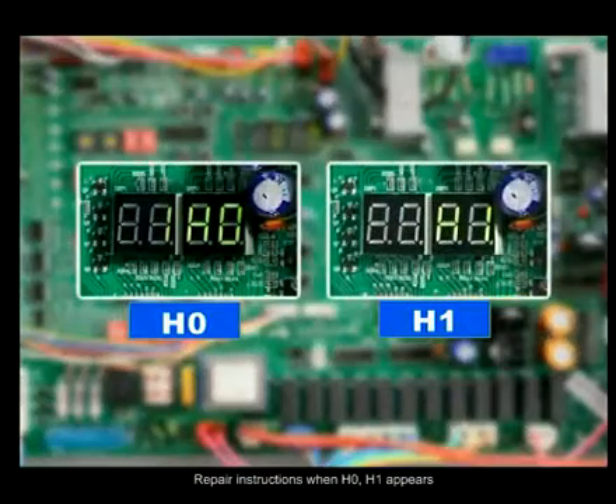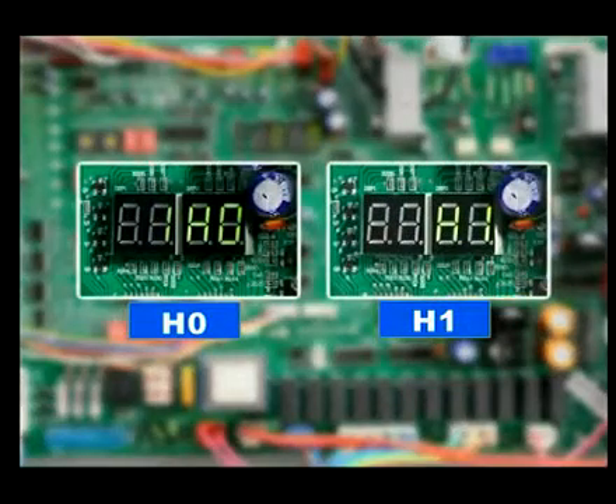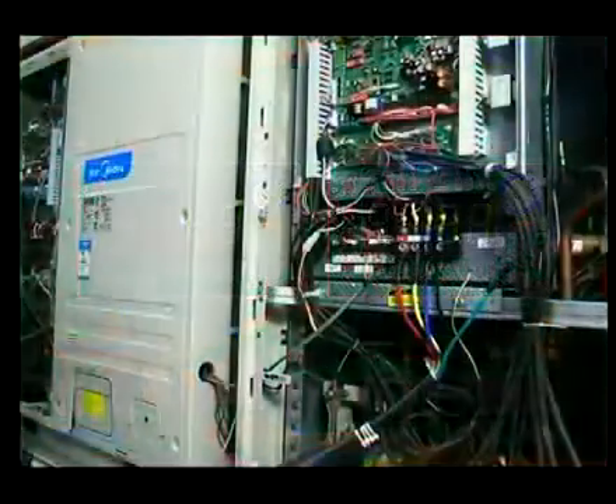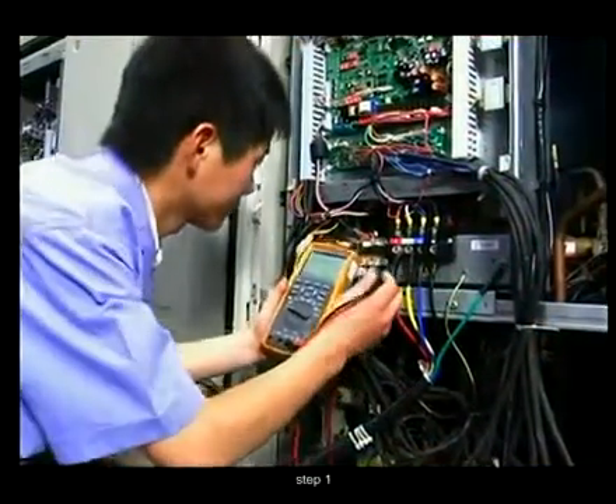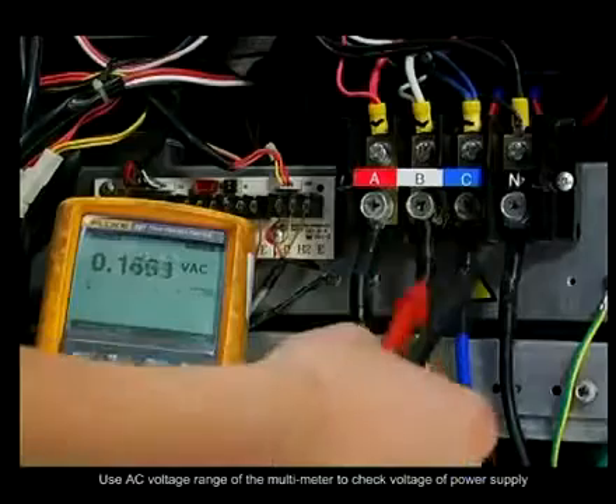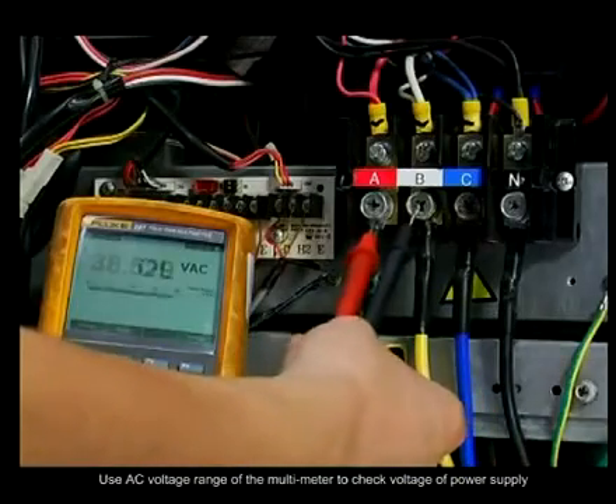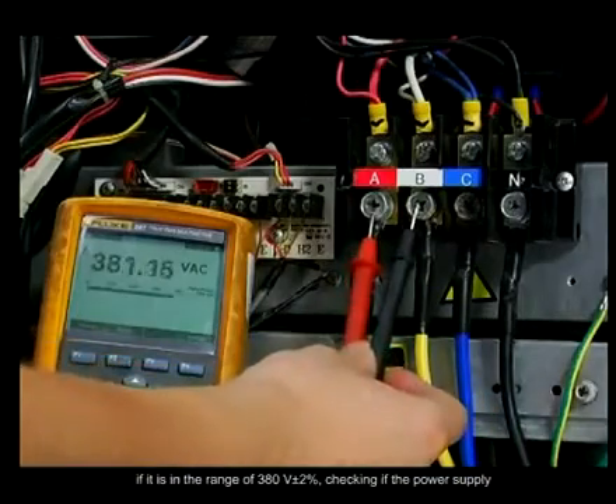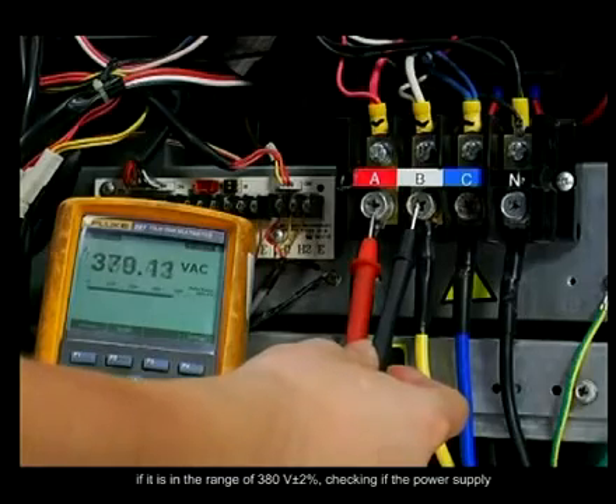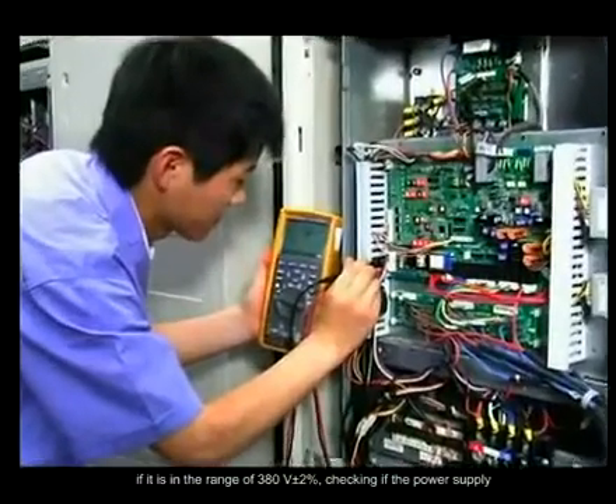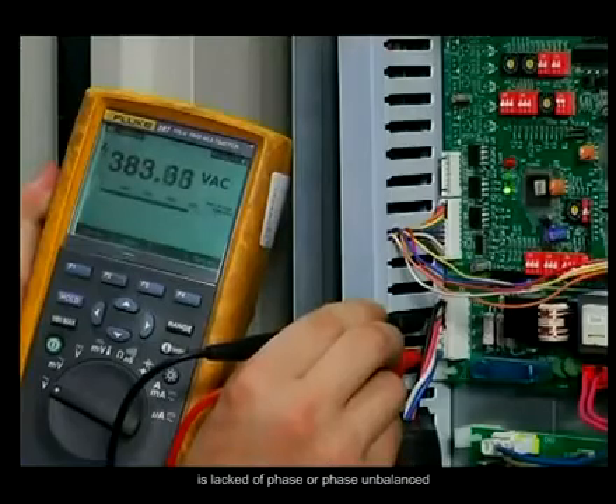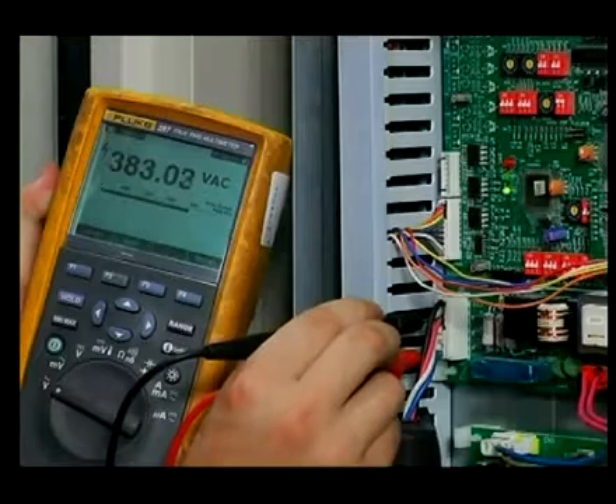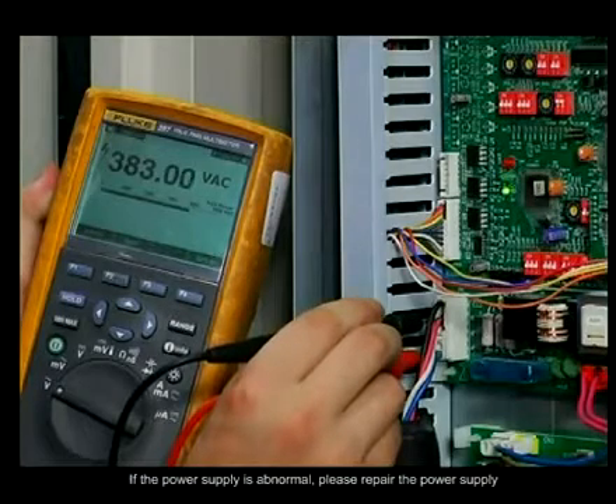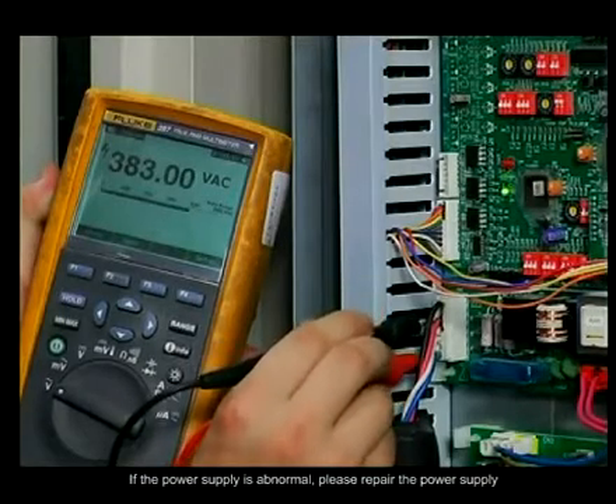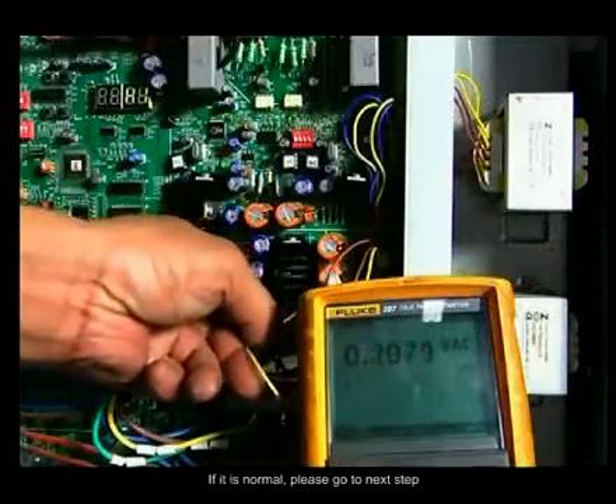Repair instructions when H0, H1 appears. Step 1. Use the AC voltage range of the multimeter to check if the voltage of the power supply is in the range of 380 volts plus or minus 2%. Check if the power supply is lacking a phase or phase unbalanced. If the power supply is abnormal, please repair the power supply. If it is normal, please go to the next step.